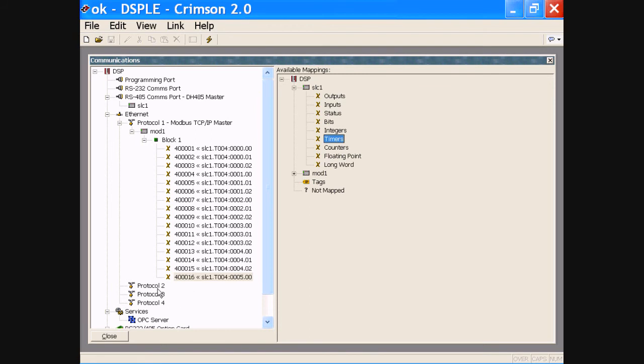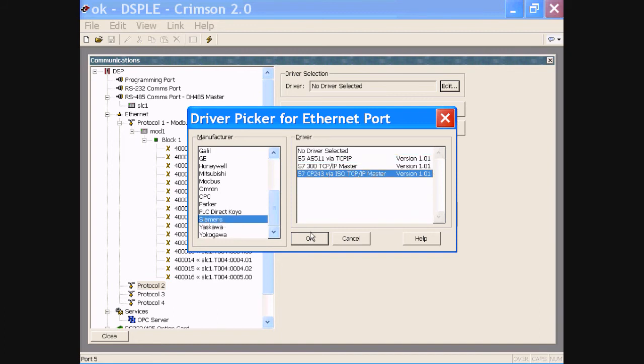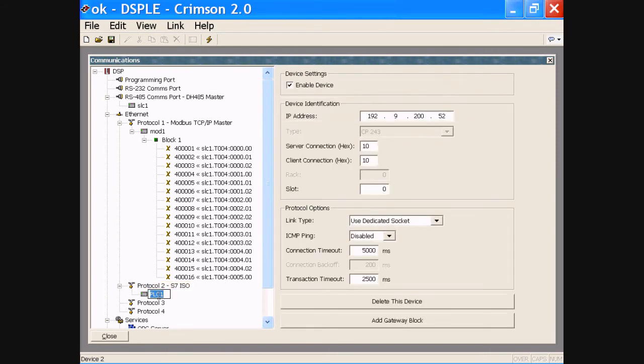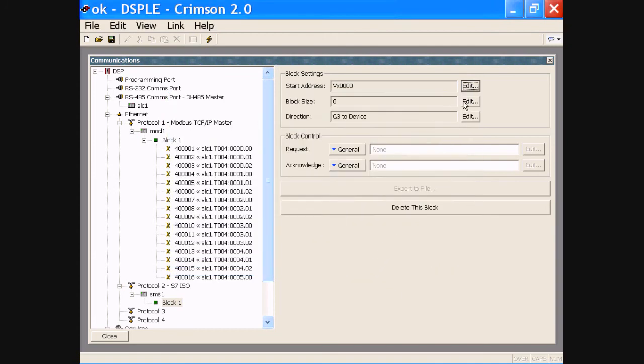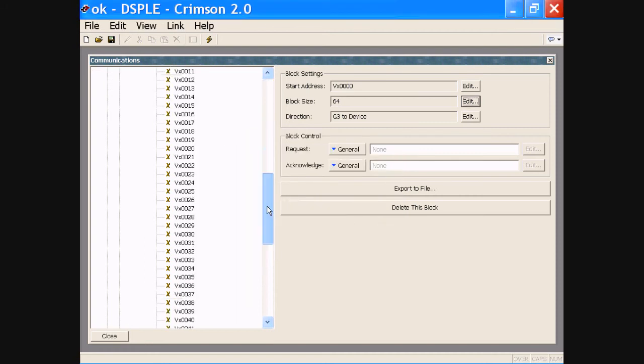Let's add another one. Let's say we've got a Siemens PLC on our floor too. Pick an S7-200 and give it a name — SMS1. Add a gateway block into it. Siemens has variable memory locations; we'll start at V0. Let's map 64 of them this time. So now we have 64 V-memory locations.